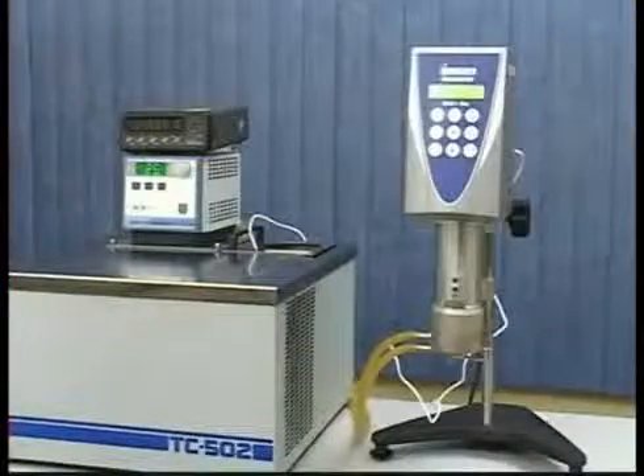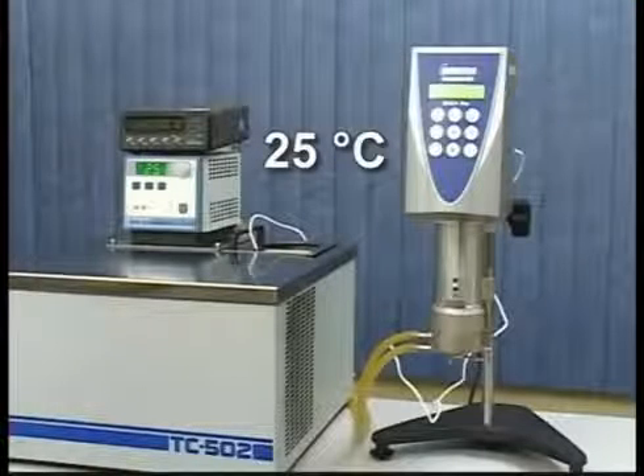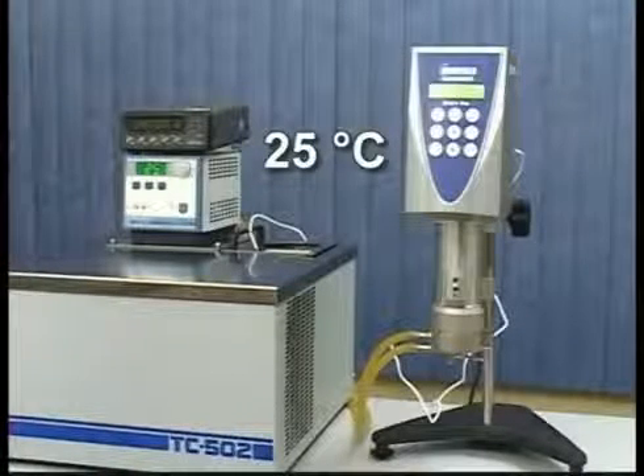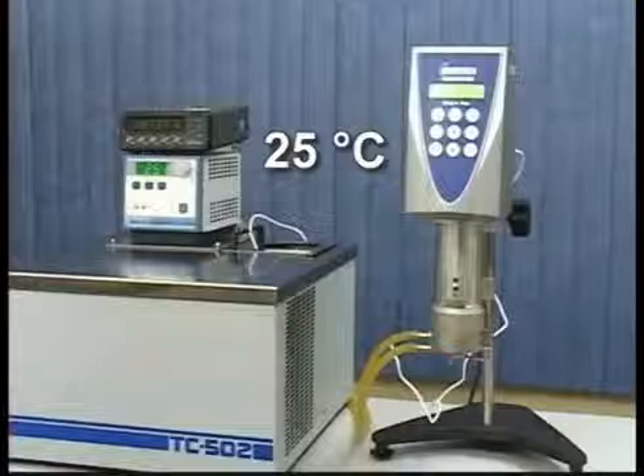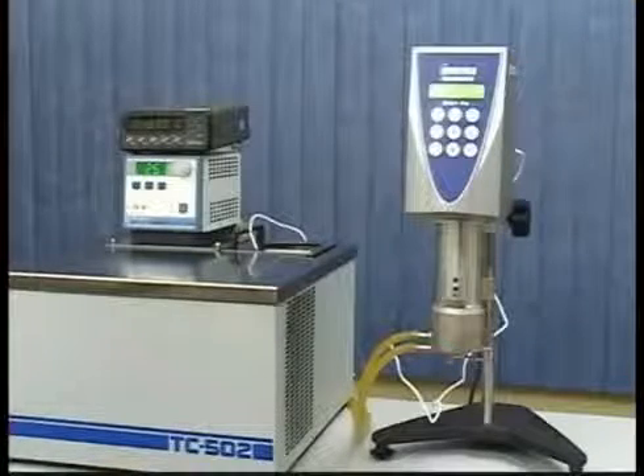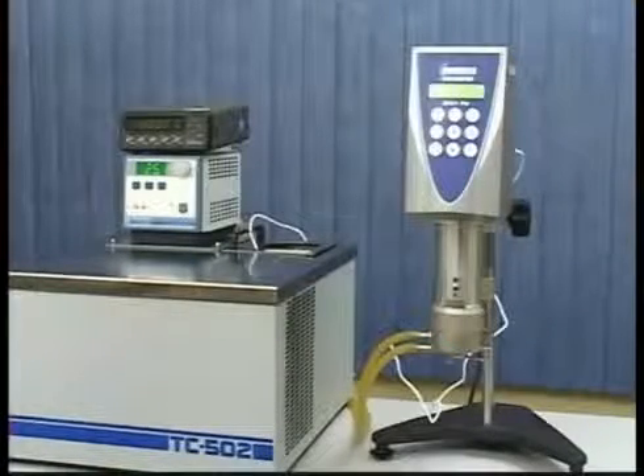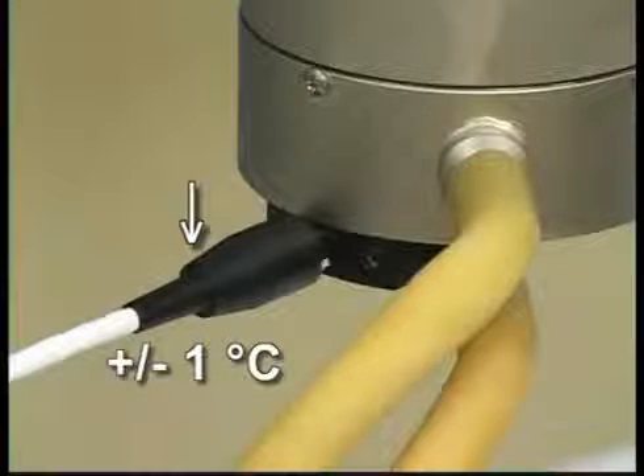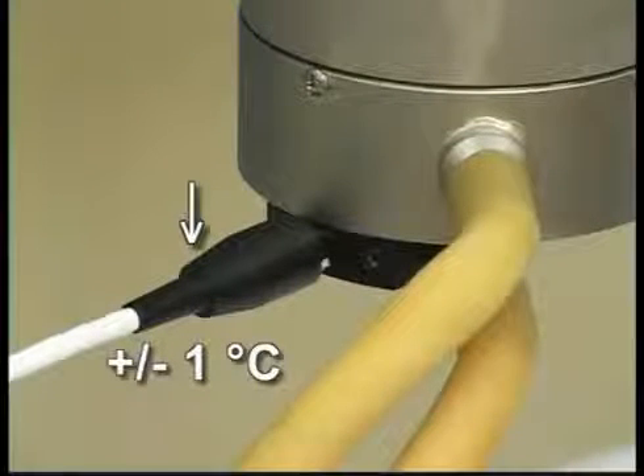For proper temperature equilibration, the fluid and cone all need to be equilibrated at 25 degrees Celsius. The viscosity standards are very sensitive to temperature. The embedded temperature probe in the cup of the Brookfield cone plate is accurate to plus or minus 1 degree centigrade.